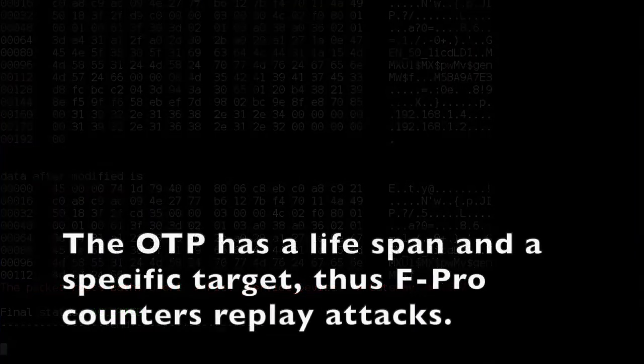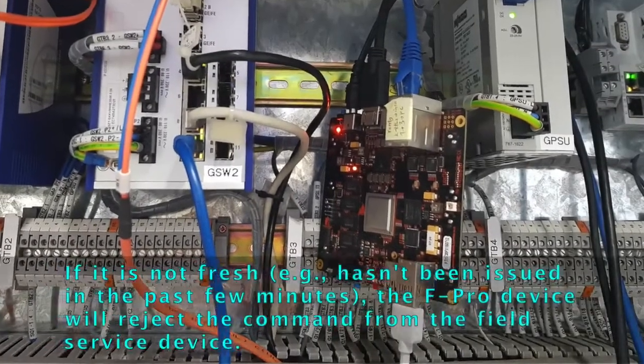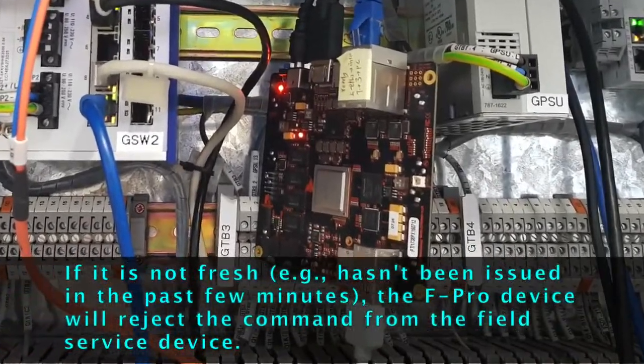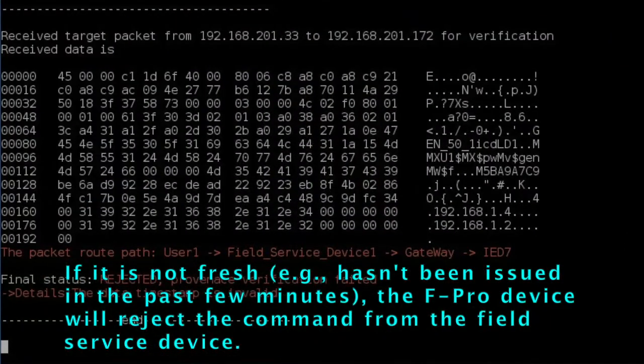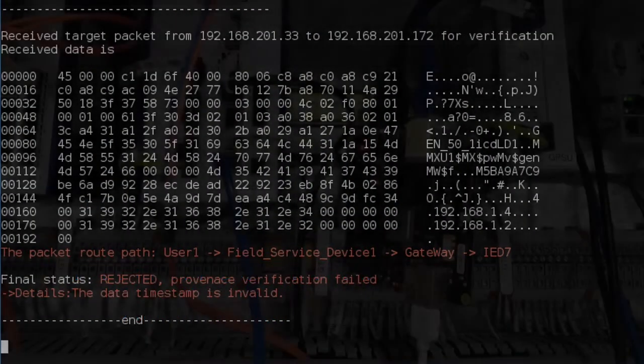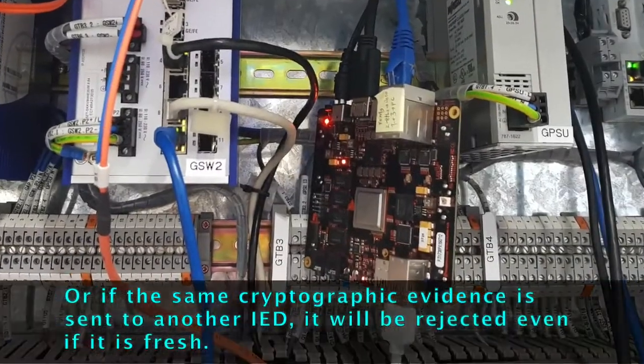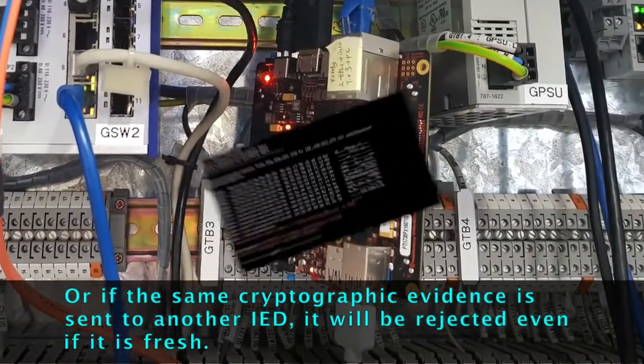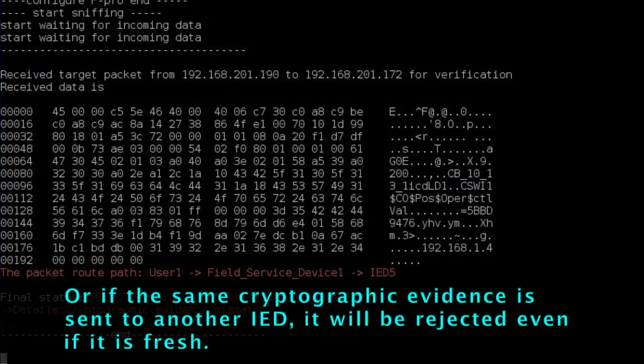The one-time password has a lifespan and a specific target, thus F-Pro counters replay attacks. If it isn't fresh, hasn't been issued in the past few minutes, the F-Pro device will reject the command from the field service device. Or if the same cryptographic evidence is sent to another IED, it will be rejected even if it is fresh.